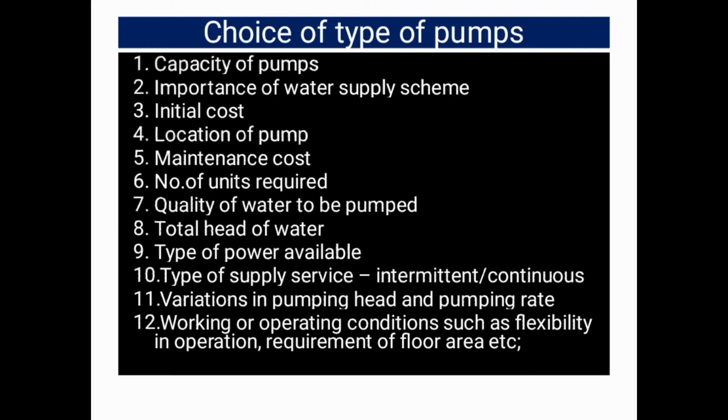Capacity, importance of water supply, initial cost, maintenance cost, location of pump, number of units required, quality of water to be pumped, then total head of water. Total head means suction head plus delivery head plus head loss due to friction. And then the type of power available, type of supply service, whether intermittent or continuous, variations in pumping head and pumping rate, working or operating conditions such as flexibility in operation, and requirement of floor area, etc.